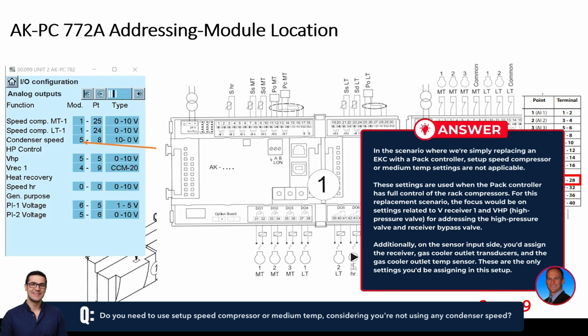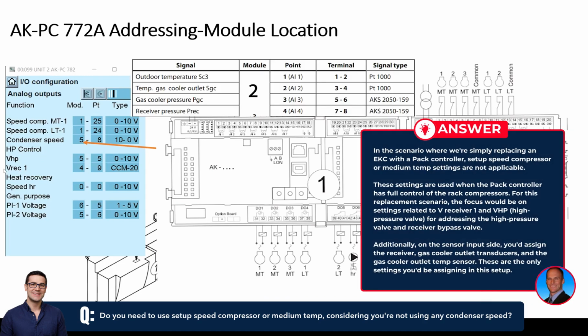This would be settings or application options that we'd use if we were taking full control of the rack. So if the pack controller had control of all the compressors on the low temp, medium temp side, that would be setup options that you're seeing here that would be used. So the only one really on this one would be the V receiver 1 and VHP. So this is your high pressure valve, VHP, and then VREC would be your receiver bypass valve. Yeah, so those are the two. If you're just doing that replacement, you need to set up those addressing. That's exactly those valves. Right.